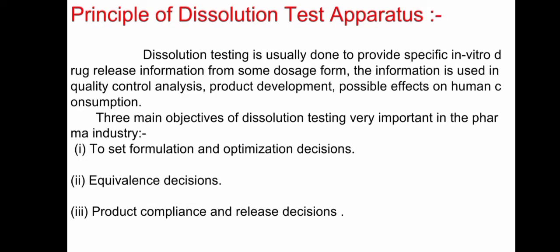Principle of dissolution test apparatus. Dissolution testing is usually done to provide specific in vitro drug release information from a dosage form. The information is used in quality control analysis, product development, and possible effects on human consumption. Three main objectives of dissolution testing, very important in the pharma industry: 1. Formulation and optimization decisions. 2. Equivalence decisions. 3. Product compliance and release decisions.